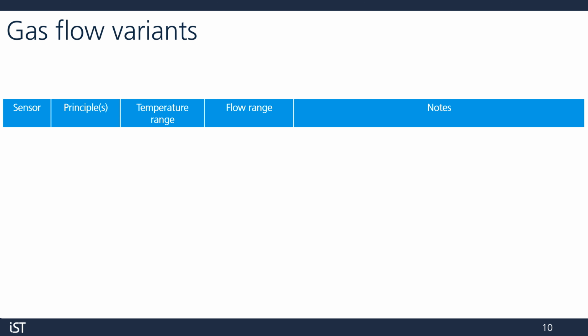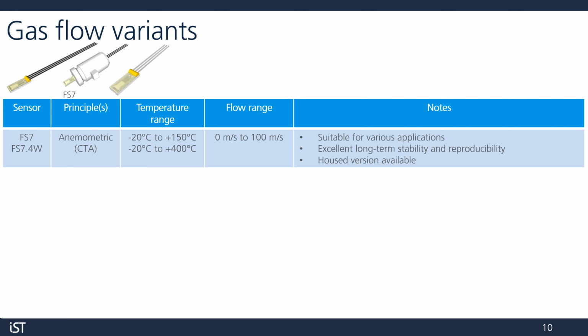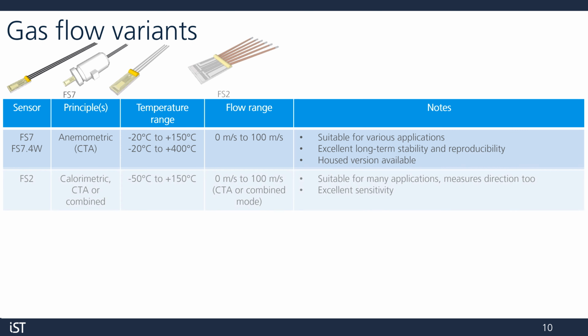Here I'll just give a quick overview of the available standard elements. First up, we have the FS7, which is our all-rounder suitable for most applications. A few variants are available, including a housed version and a high temperature version usable up to 400 degrees Celsius. Next, the FS2, which is a similar construction to the FS7, but it can be operated in calorimetric, CTA, or combined mode, depending on your application. Like I mentioned before, the calorimetric sensors can tell us the flow direction too.